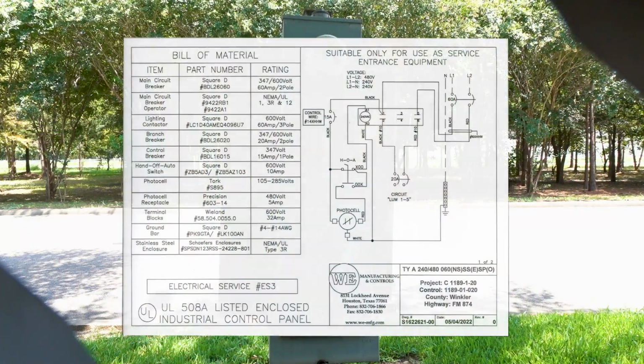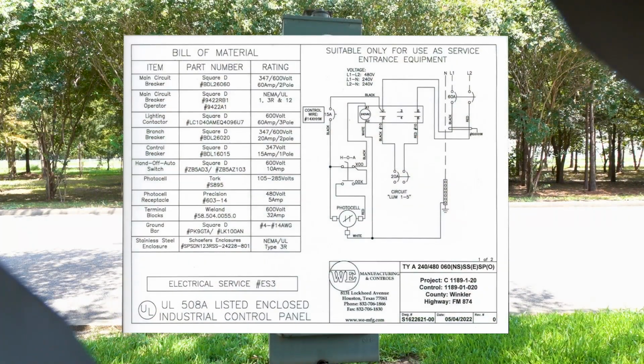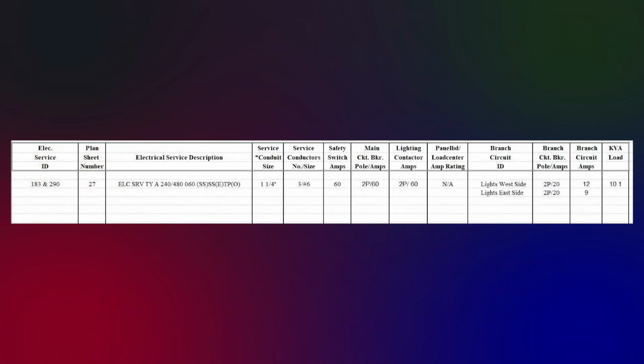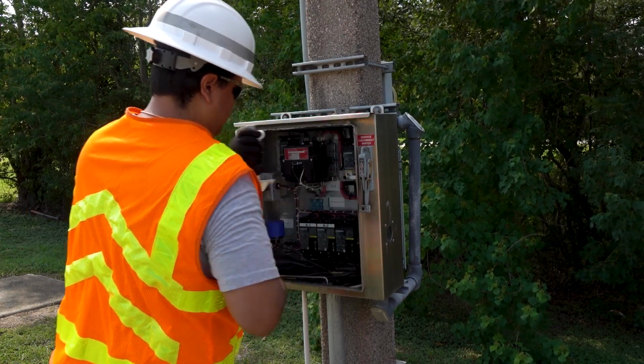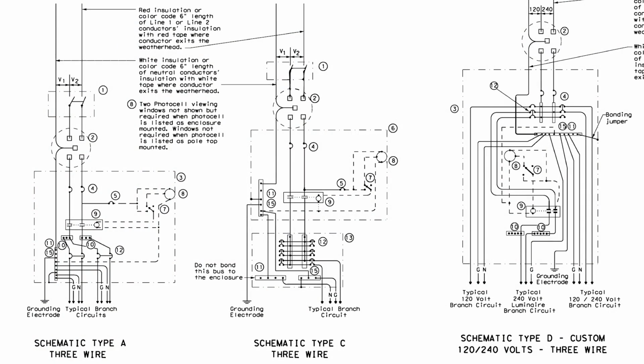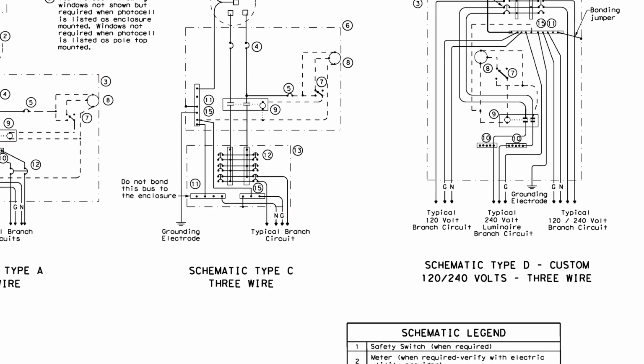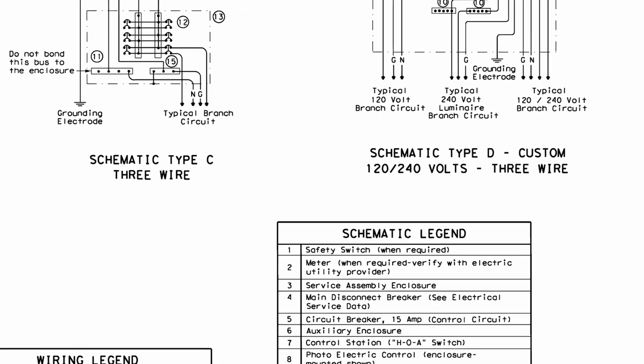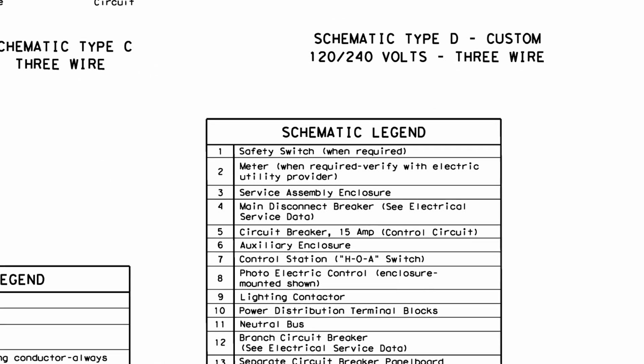The inspector should verify that the manufacturer's line drawing matches the electrical service data chart in the plans, as well as verifying the service manufacturer is listed on TxDOT's material producers list. Before we begin to inspect a Type A service, we will review its schematic drawing on the ED6 standard sheet. The schematic legend for this drawing is in the lower center of ED6 and gives the names of each component.